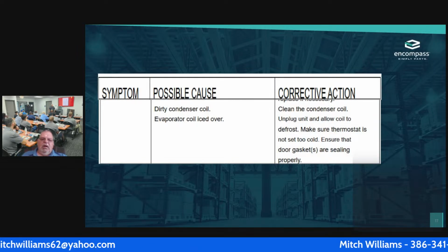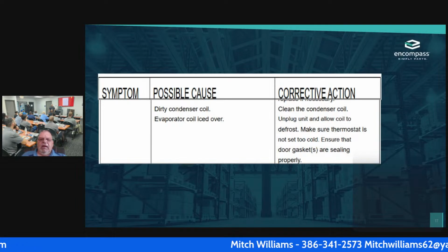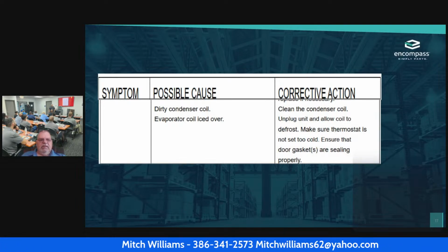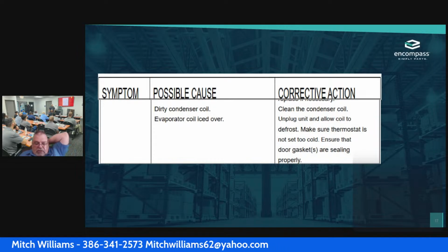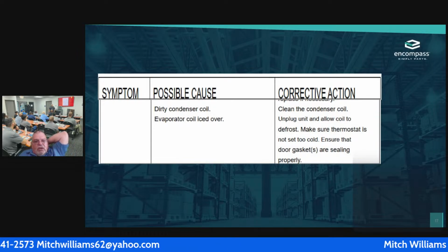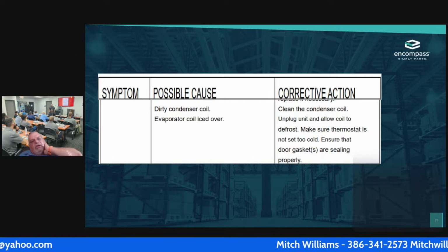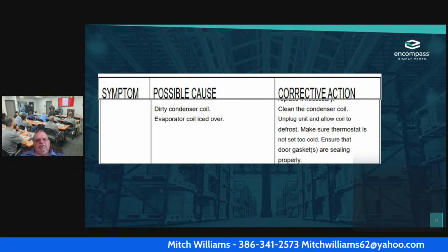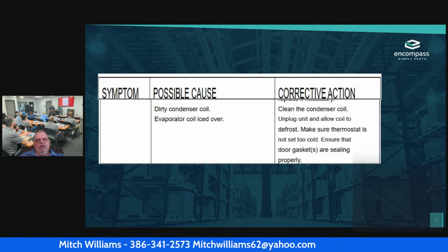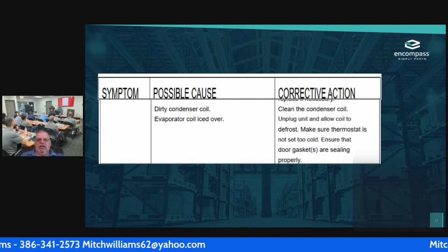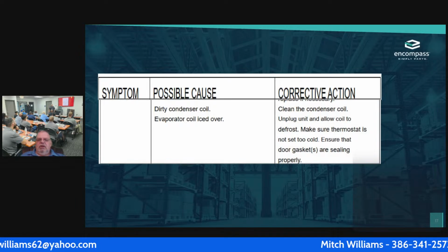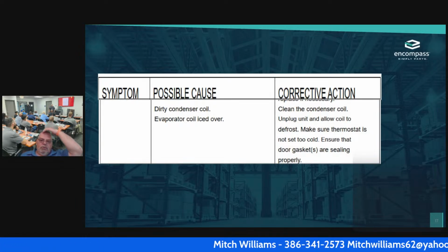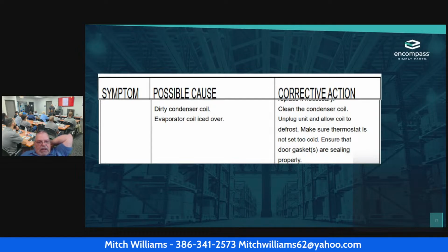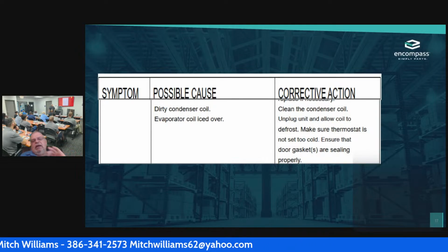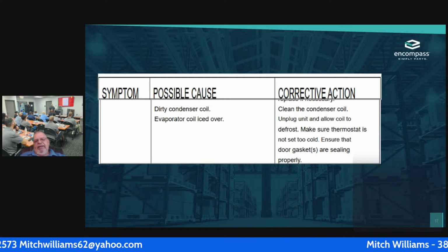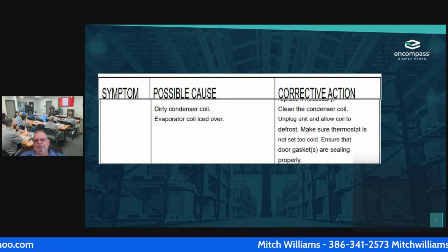So it could be a dirty condenser coil. Of course, if that's the case, I'm going to need to clean the condenser coil and the fins and make sure that I get all of that done. We kind of went through all of that. Or it could be that the evaporator coil is iced over. Okay. If that's it, then I'm going to have to do one of two things. I can unplug the unit and allow the coil to defrost. One of the other things that I can do is go out to the truck and get my steamer. I'm going to have to take the food out.